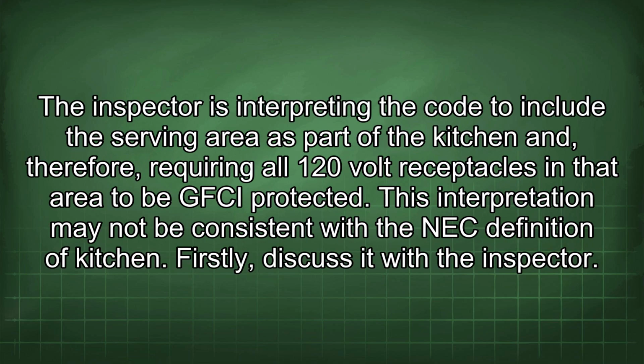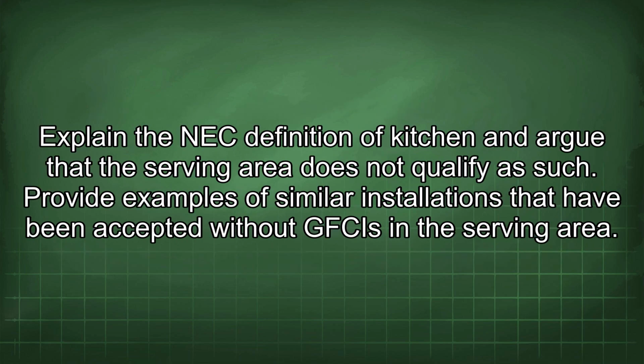The inspector is interpreting the code to include the serving area as part of the kitchen and, therefore, requiring all 120-volt receptacles in that area to be GFCI protected. This interpretation may not be consistent with the NEC definition of kitchen. Firstly, discuss it with the inspector. Explain the NEC definition of kitchen and argue that the serving area does not qualify as such. Provide examples of similar installations that have been accepted without GFCIs in the serving area.